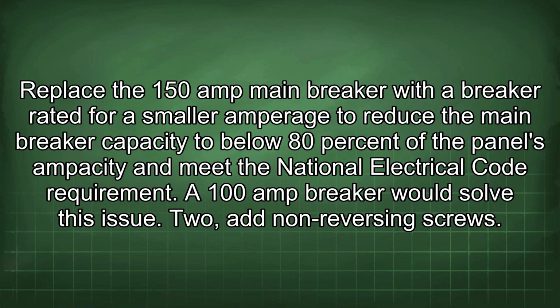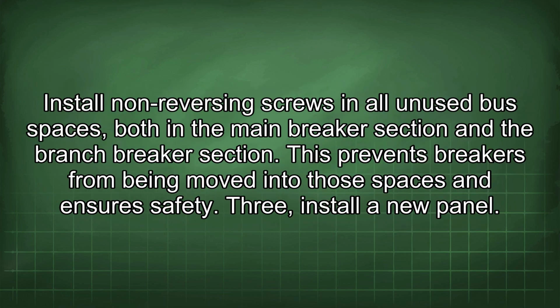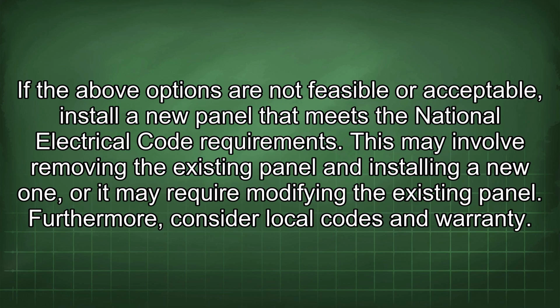2. Add non-reversing screws. Install non-reversing screws in all unused bus spaces, both in the main breaker section and the branch breaker section. This prevents breakers from being moved into those spaces and ensures safety. 3. Install a new panel. If the above options are not feasible or acceptable, install a new panel that meets the National Electrical Code requirements. This may involve removing the existing panel and installing a new one, or it may require modifying the existing panel.